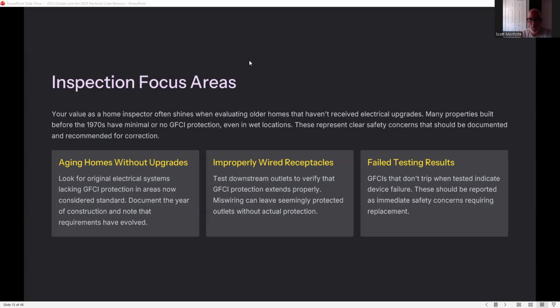Improperly wired receptacles, I do training. I'm a supervisor, so I will have interns, and they will say, all the other outlets are GFCI protected. I tested this, and I don't see any other buttons, so I make them test every single outlet. And sure enough, there's always one that's not connected. And then the GFCIs that don't trip, they get old, and they freeze up and they don't reset. I've made it a habit that if I'm in a garage and there's a freezer with $5,000 worth of meat, I'm not testing that GFCI outlet. There's just no way, because I'm not buying them a whole freezer full of meat. So we'll talk about that as we go along.